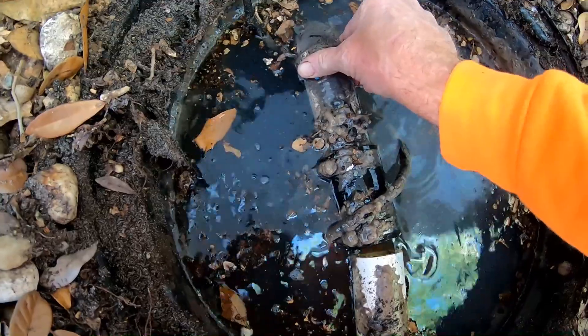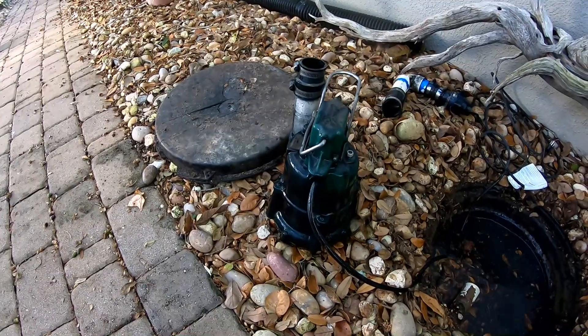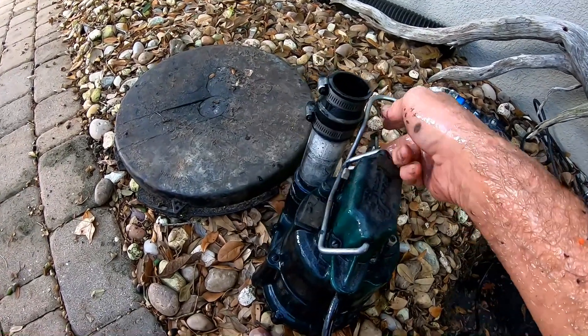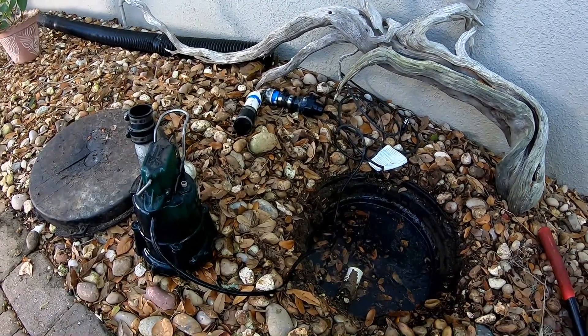If you search back through the videos you'll see this install about three years ago — we added catch basins, it all comes over to the sump pump, the pump lifts it up and sends it all the way back to the lake. Okay, let's take a look. You can see what happened here: the pump actually came loose, you see that fitting — it came off — and it probably burned out the pump. I'm going to pull the pump. We'll start by unplugging it. So there's the Zoeller M98. Now we need to troubleshoot and find out why this pump failed.